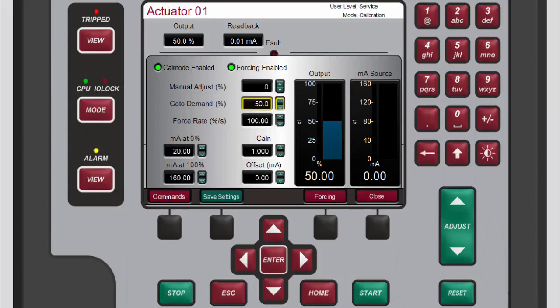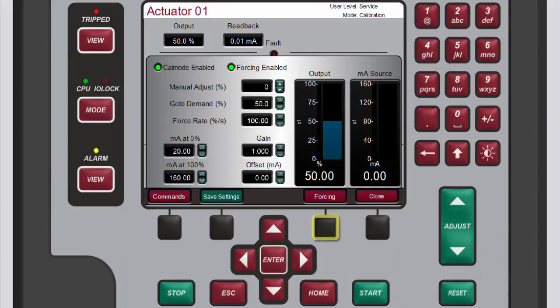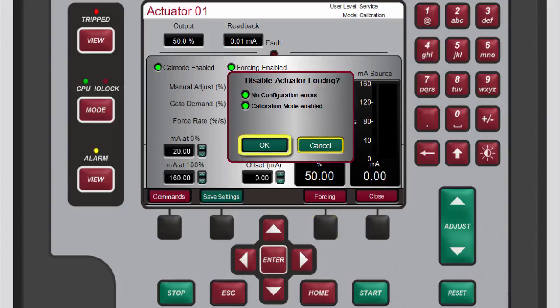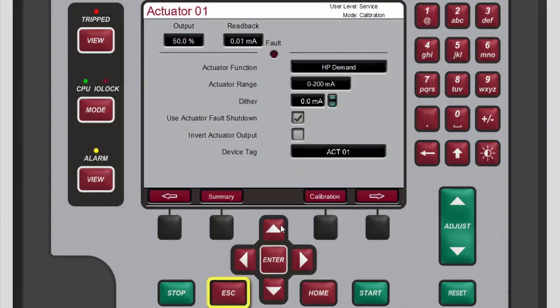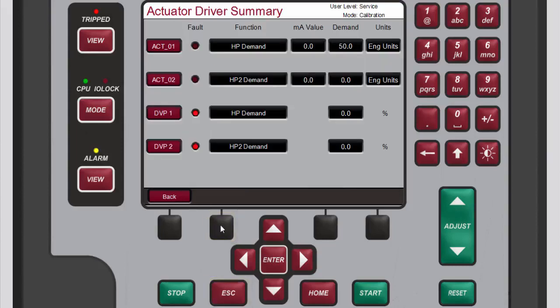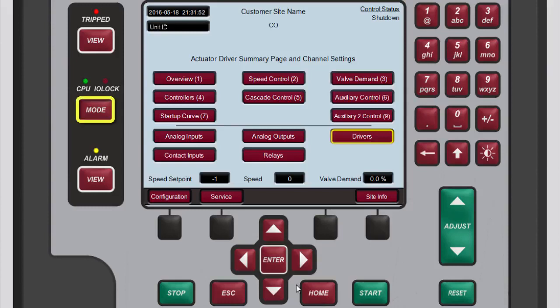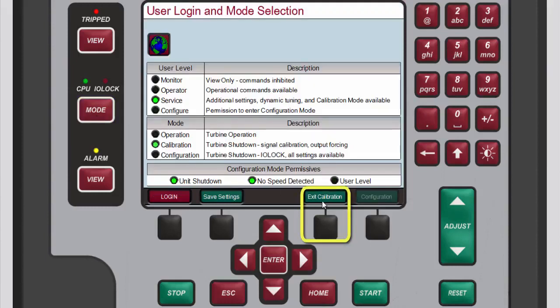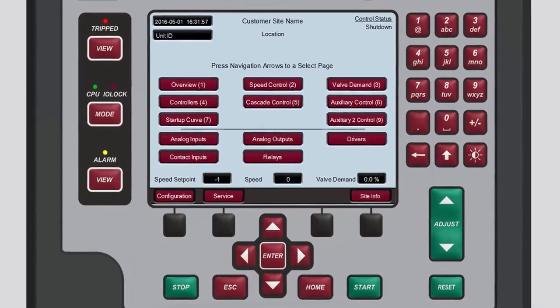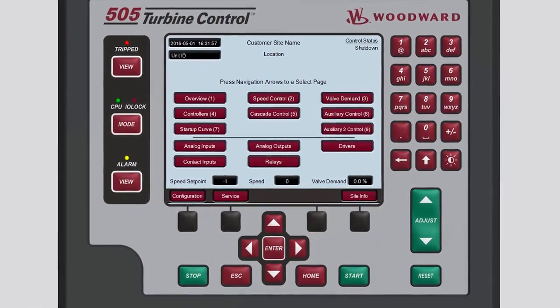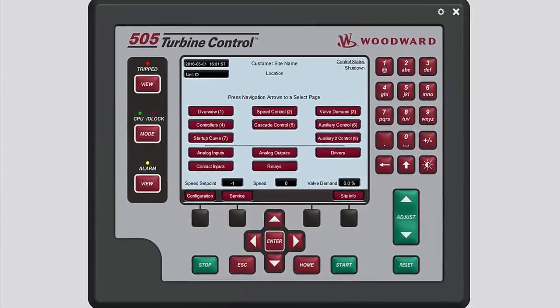If you made changes, press the black function key below save settings, then disable forcing by pressing the black function key below forcing. Press escape or the black function key below summary to return to the actuator driver summary screen to calibrate the second actuator if it is being used. When finished, press home to return to the main screen. Remember to exit calibration mode when you are done making changes. You now know the basics of configuring and calibrating actuator drivers — please be sure to view the other tutorials for more information.